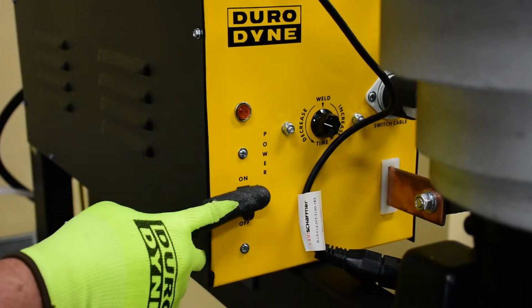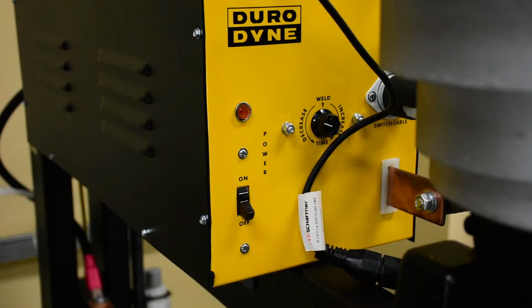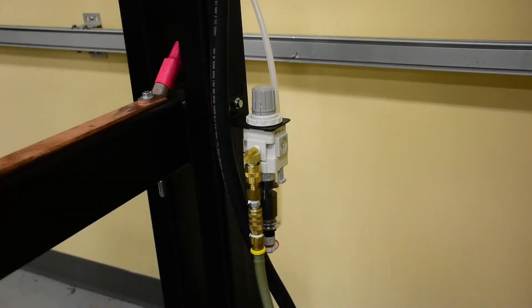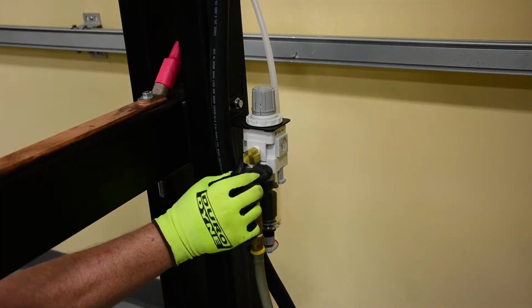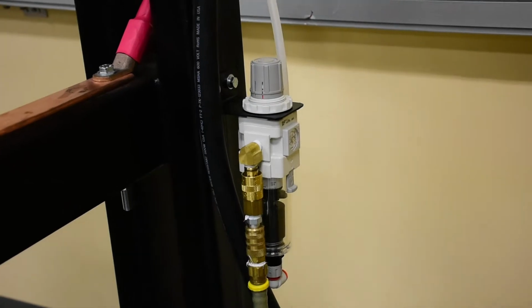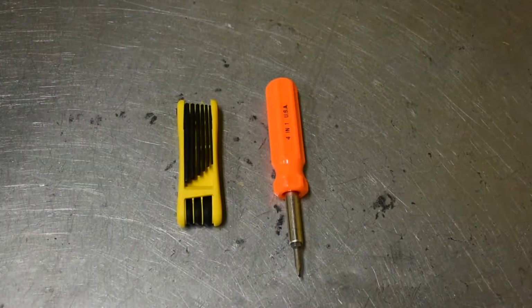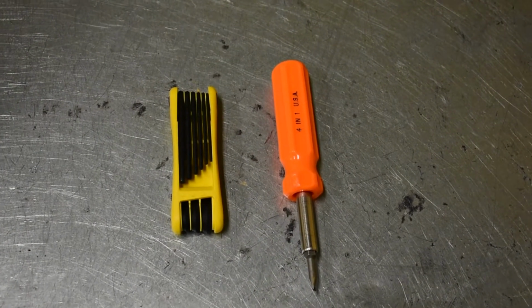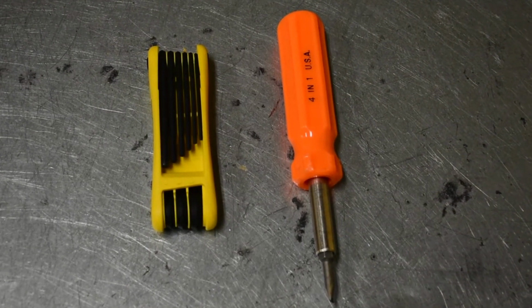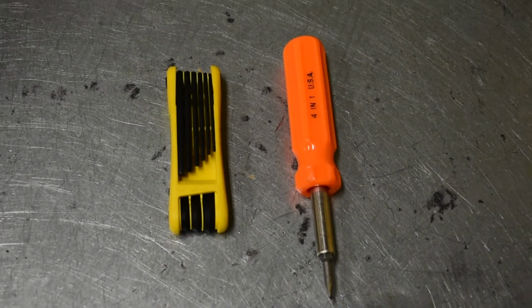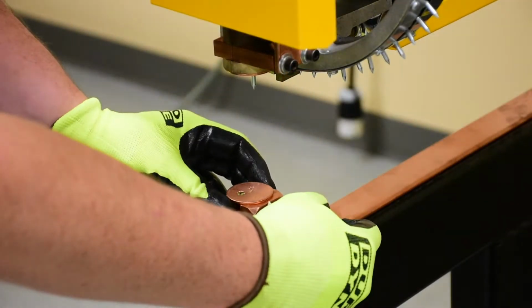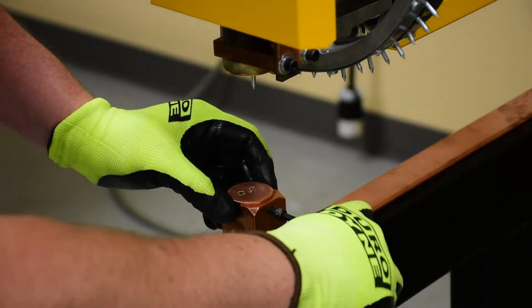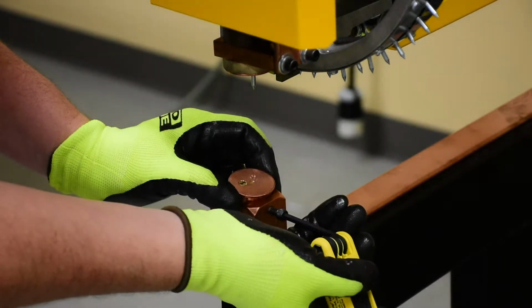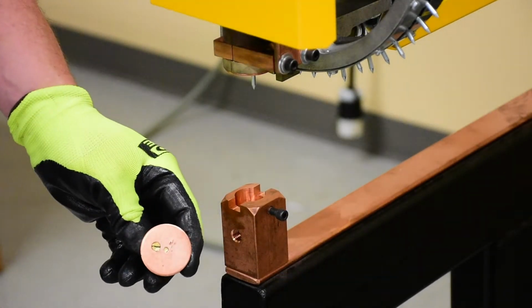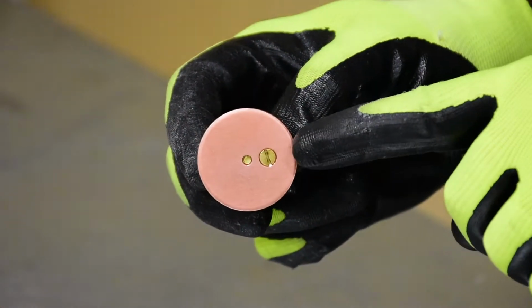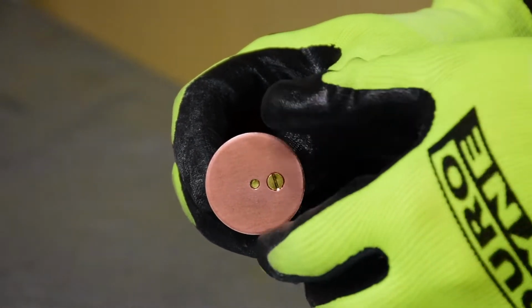Now let's get to changing that plate. For your safety, always turn the power off to your Duro Dyne pin spotter at the on and off switch, and then release the air by using the quick slide release on your air regulator. You'll require a few tools to replace the lower weld tip: a flathead screwdriver and an Allen wrench size 3/32 and 3/16. Begin by loosening the set screw on the mandrel with a 3/16 inch Allen wrench. Remove the lower weld tip from the mandrel. You will see the 3 additional set screws that must be loosened in order to remove the plate.